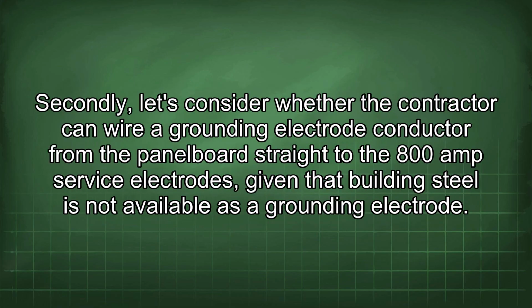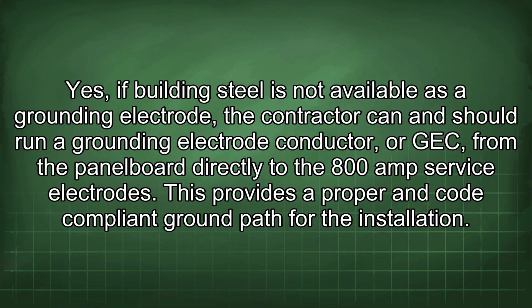Secondly, let's consider whether the contractor can wire a grounding electrode conductor from the panel board straight to the 800 amp service electrodes, given that building steel is not available as a grounding electrode. Yes, if building steel is not available as a grounding electrode, the contractor can and should run a grounding electrode conductor, or GEC, from the panel board directly to the 800 amp service electrodes. This provides a proper and code-compliant ground path for the installation.